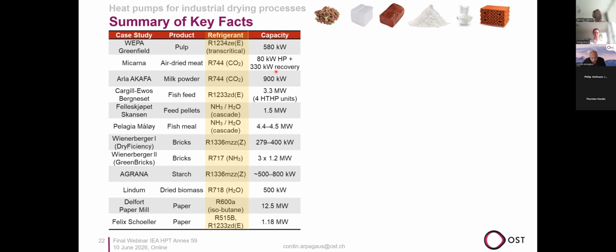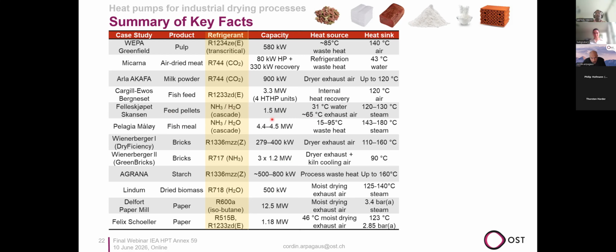The capacities are in the several hundred kilowatt heating range, some even in the megawatt scale. The heat sources are typically exhaust humid air from the dryers, or some waste heat at temperatures suitable for heat pump integration. The heat sink temperatures go up to 140, 160, 180, or 120 degrees. A special case is air drying from Switzerland at 43 degrees, cold drying.